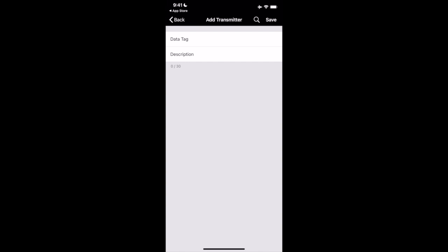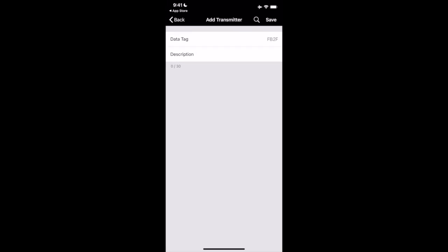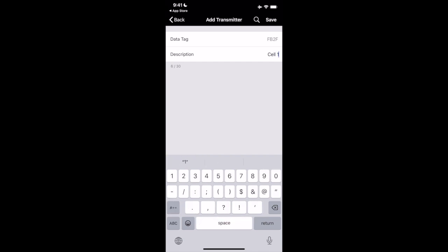So the data tag, you'll see, it'll say ID and there will be six digits behind it. The data tag is the last four digits of that six digit ID. And then we can add a description. The easier way, which I'll take you through, we're going to hit the magnifying glass in the top right corner. That'll bring us here. We will see all the transmitters that we can see right now. So currently we're seeing my load cell over here with the FB2F. So we're going to come in here. If we click our three dots, that opens us up. I believe you can actually just click anywhere off that one. So we're going to see our data tag, FB2F in description. We're going to click on that and we're going to call it cell one.